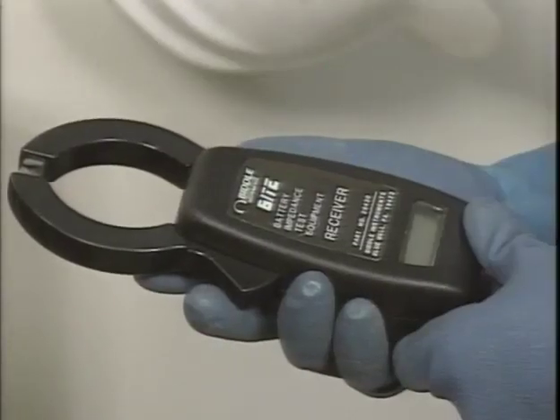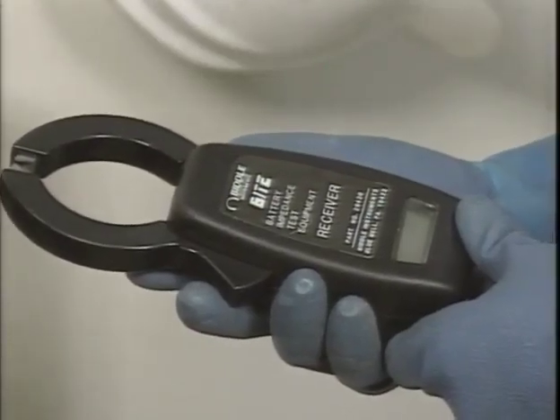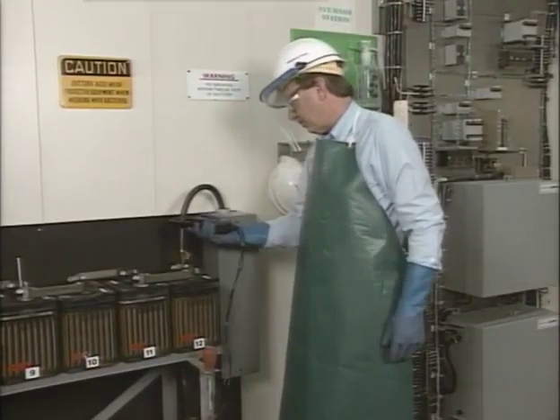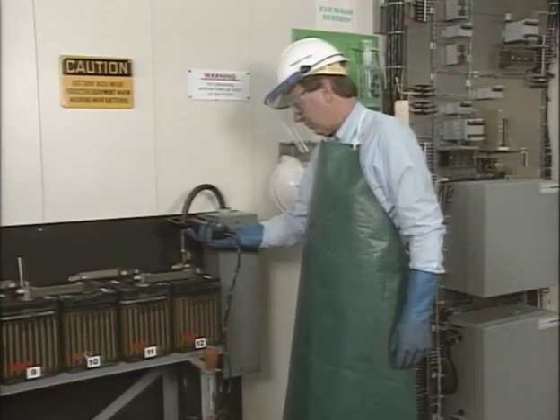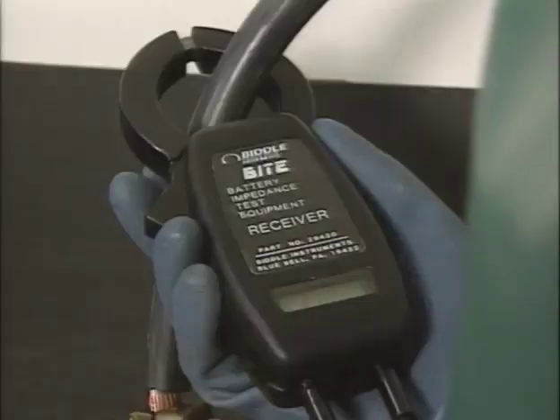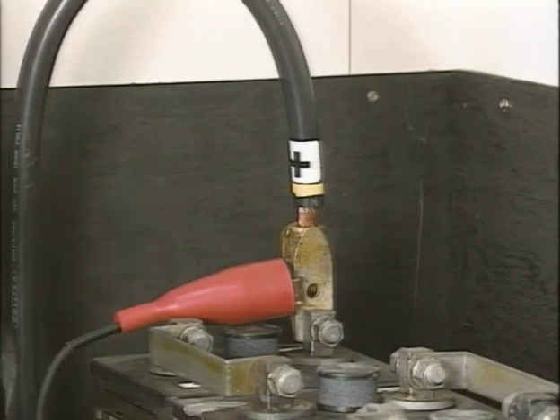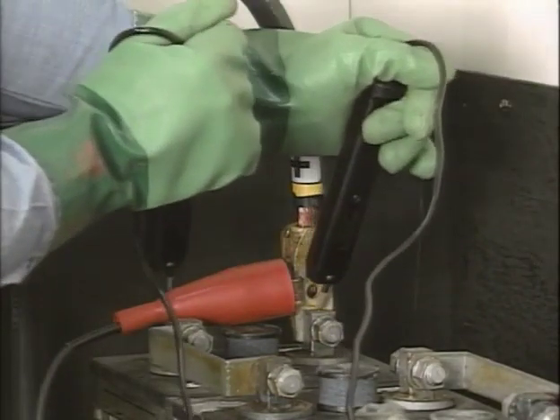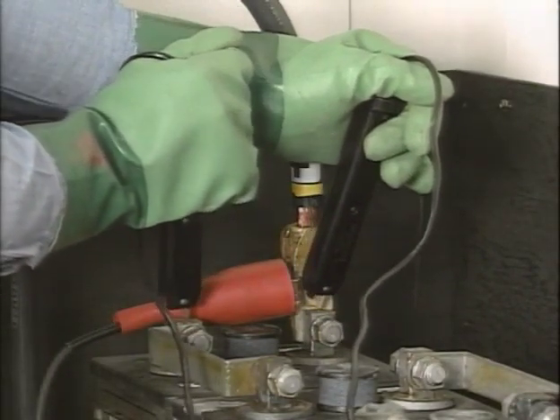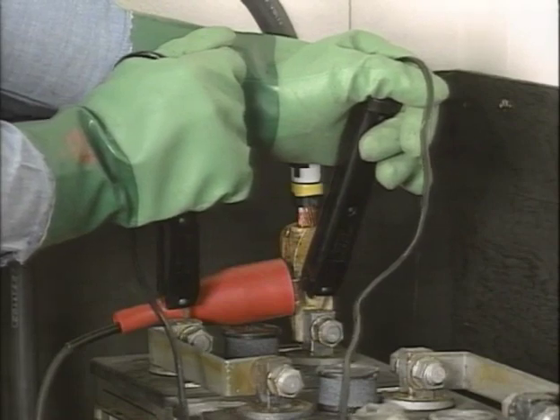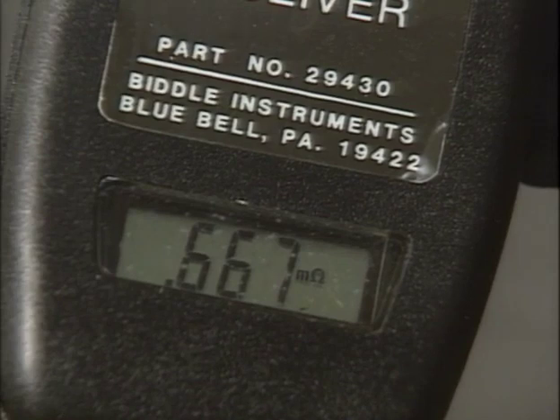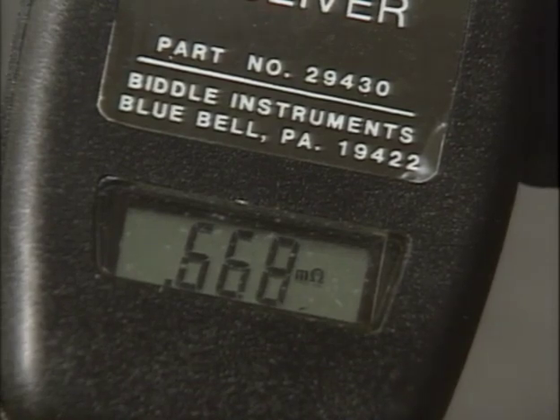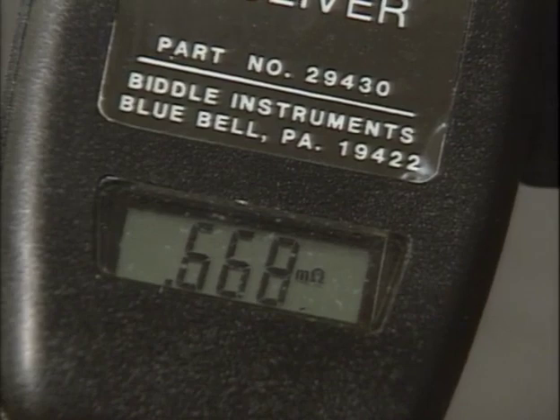A third component of the test set is the receiver. Jaws on the receiver are clamped around an inter-cell connector or an inter-tier connector. The receiver then measures the AC current flowing through the battery. Voltage probes connected to the receiver are placed firmly across the terminals of the cell being tested. The receiver then also measures the AC voltage across the cell. The receiver uses the AC current and AC voltage values to internally compute the cell impedance. It then displays the impedance in milliohms.